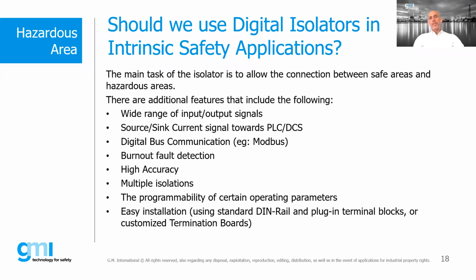But there are also differences from the past. You were probably also used to applying Zener barriers. The Zener is just an isolator between the hazardous area and the safe area. In this case, the digital isolators also include other features, like wide range input-output signals, and source or sink current signal to the PLC DCS. So you can have different options because the PLC DCS is also designed in different ways. Some are sink, so they can or must be coupled with a source signal, and some are source, so they must be coupled with a sink signal. So there are different associations.